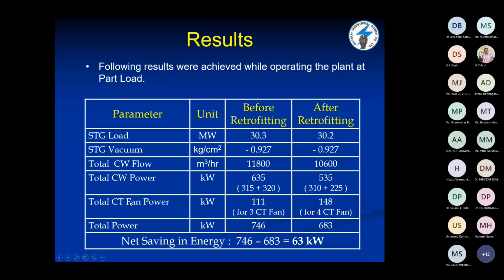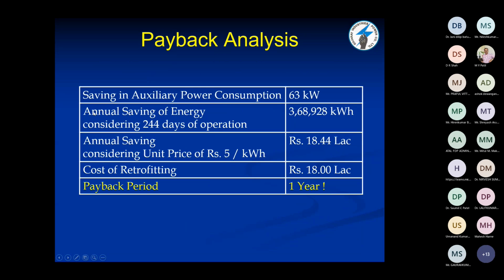Total CW cooling tower fan power consumption has increased slightly, but the total power, that was 746 including the power consumption of the cooling tower fan, now shows a net saving of 63 kilowatt. Okay. Now considering the plant is running for 244 days and auxiliary power consumption is 63 kilowatt, that is a total saving of 3,68,928 kilowatt hours. And because we are power generating, the unit cost is very low from our end. We consider 5 rupees per kilowatt hour. The annual saving was 18.44 lakhs.